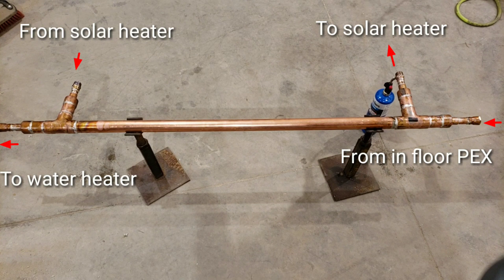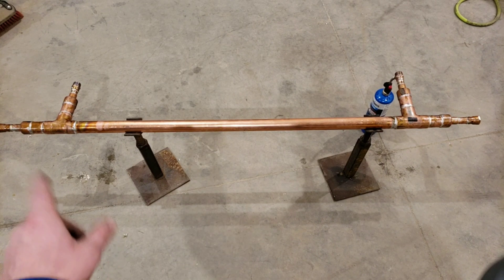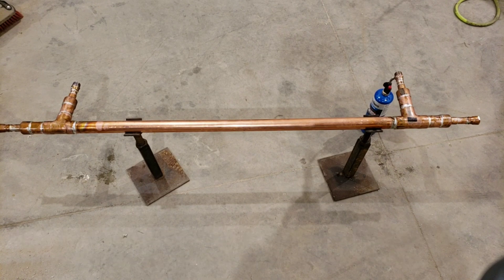That's a good way anyway — then I got a chance to pressure test it. I can plug one end and run the pressure test from the other end. To pressure test, I just use an air compressor — I have a plug for one end and a fitting for the other that I can run air into and then check it. You can do it with water, but the only problem is if you find a leak, you've got to try to drain it all out. Air is easier — I can just hit it, check the pressure, and if it's leaking out slowly, I can go along with some soapy water and see if there's any bubbles.